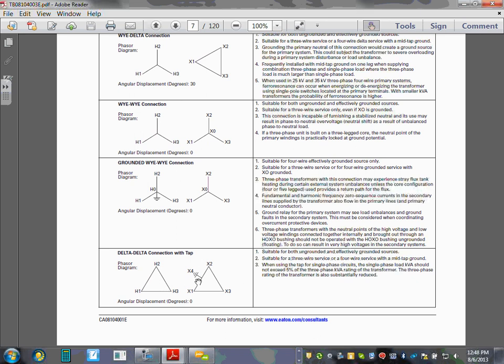center tap. I don't know if you ever designed a delta center tap system. They give it to you, I don't know. It's not fun. You might be in a situation where you have a delta center tap like this one at the bottom. The only voltage you can get out of this is 240, 120, 3 phase. So if somebody wants 240/120 3 phase, the only way you can get it is if you have a delta. They call it delta center tap.